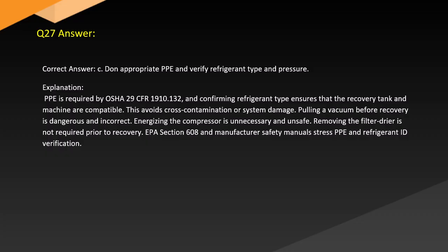Answer. Correct answer: C. Don appropriate PPE and verify refrigerant type and pressure. Explanation. PPE is required by OSHA 29 CFR 1910.132, and confirming refrigerant type ensures that the recovery tank and machine are compatible. This avoids cross-contamination or system damage. Pulling a vacuum before recovery is dangerous and incorrect. Energizing the compressor is unnecessary and unsafe. Removing the filter dryer is not required prior to recovery. EPA Section 608 and manufacturer safety manuals stress PPE and refrigerant ID verification.